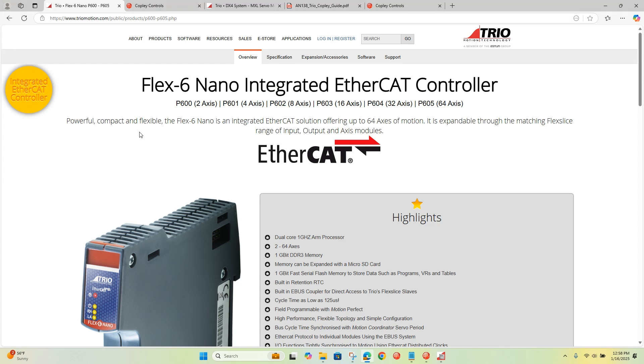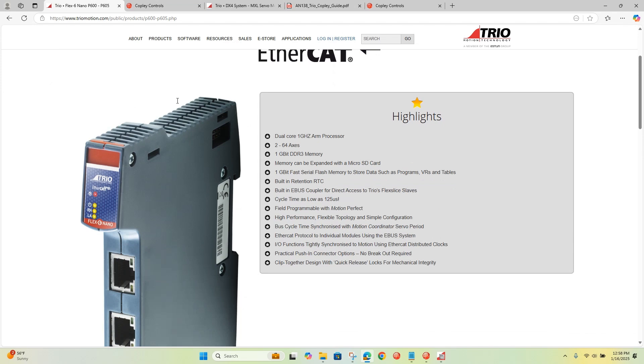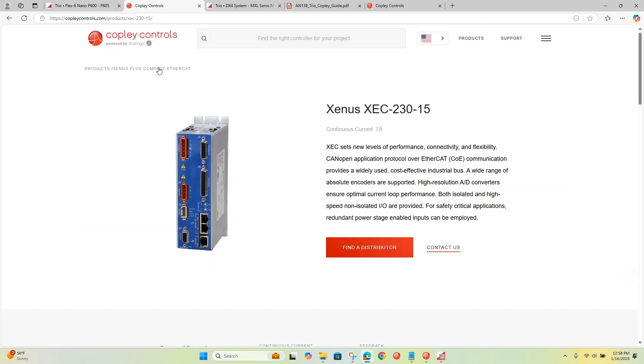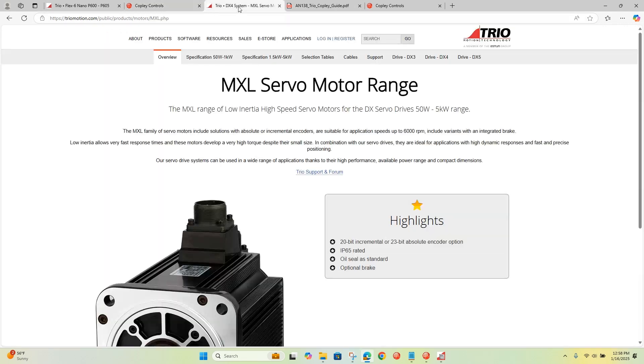This is a real-time EtherCAT main device. It can close the loop up to 125 microseconds, and has a variety of different flavors depending on how many axes you need to control. We'll be demoing the P600, which is a two-axis controller. It'll be commanding motion to the Copley XEC servo drive, and the Copley will be controlling the MXL servo motor.